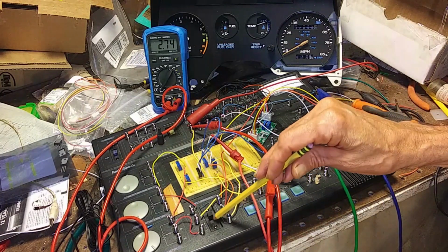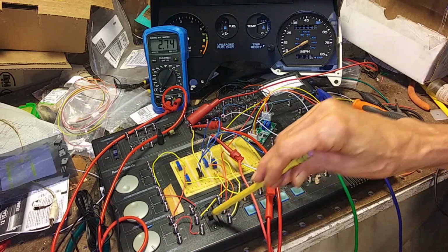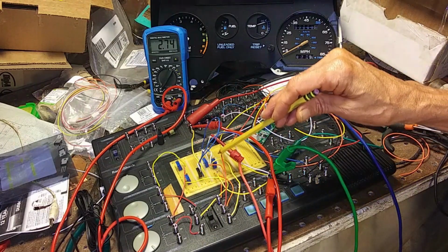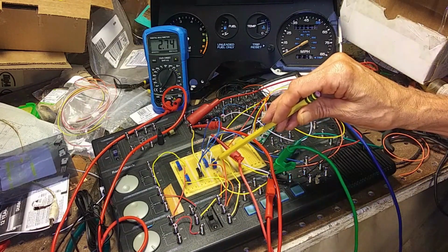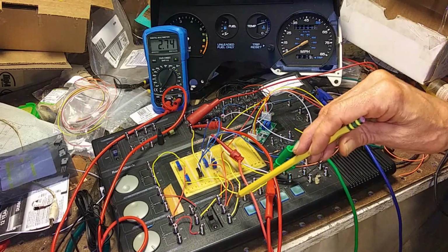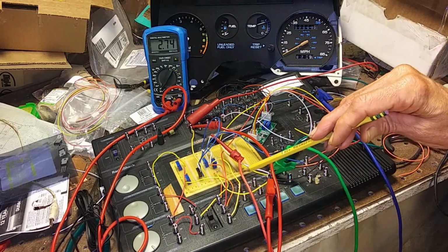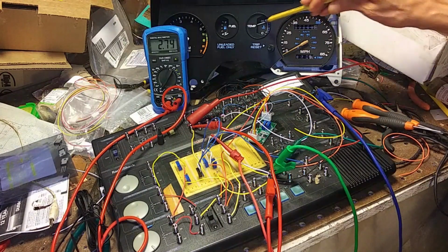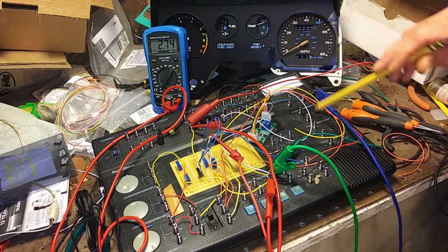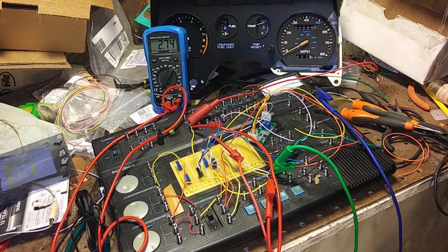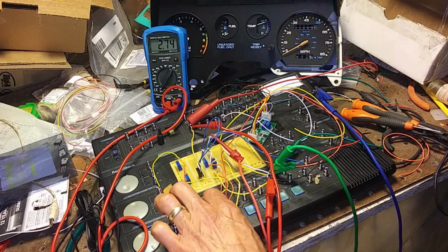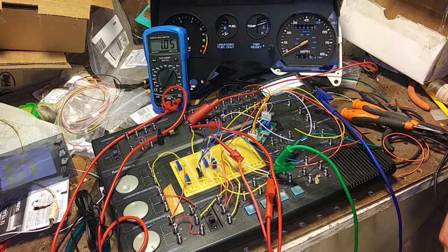So now we've got the 3560 ohm potentiometer in the circuit that duplicates the resistance of the thermistor at the high temperature of 50 degrees centigrade, and we can see that now the temperature gauge is right at the top of the normal range, which is what we want. I can switch that to the 19,000 ohm resistor, which is the resistance at the lower temperature, 10 degrees centigrade, and you can see this is slowly coming down.